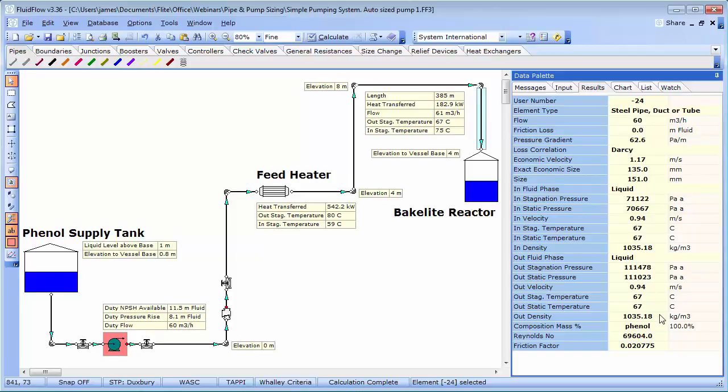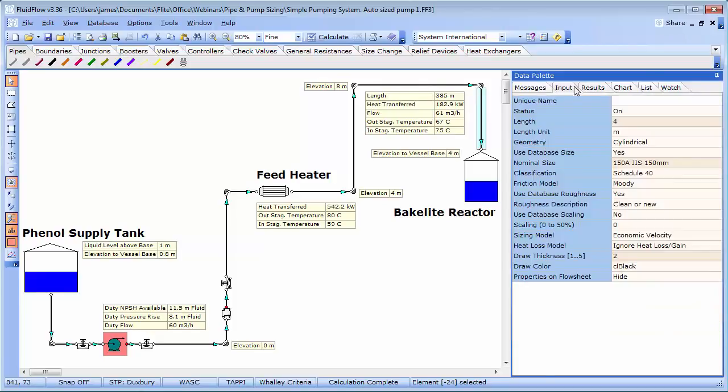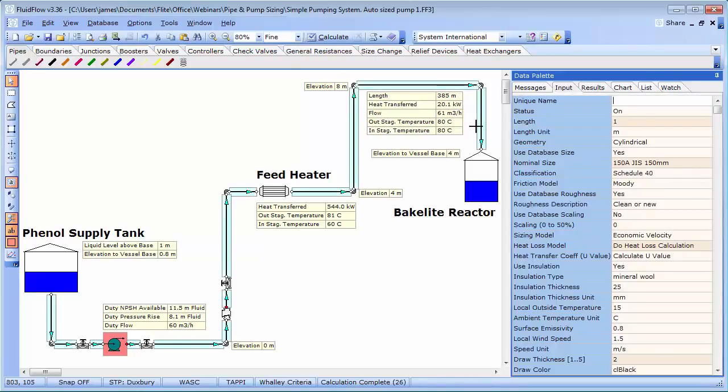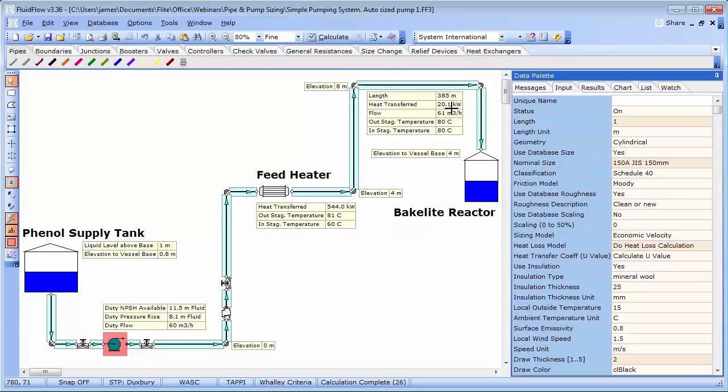Let's try adding 25 millimeters of mineral wool insulation to all pipes. And now we can see that the heat loss in this single pipe alone, which has a length of 385 meters, drops from 182 to just 20 kilowatts.